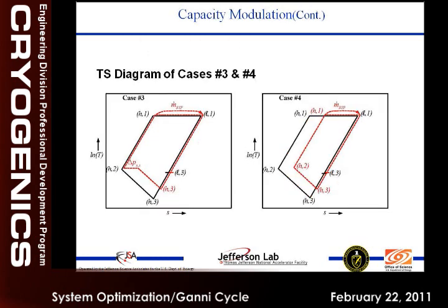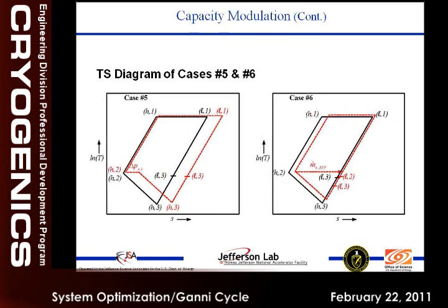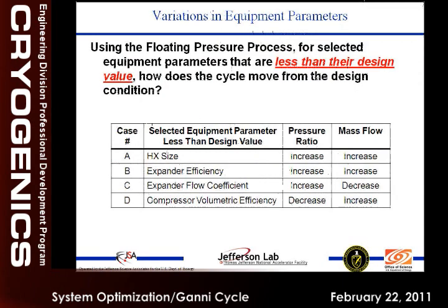So similarly, what they did is they throttled the inlet valve to the turbine to reduce the capacity because it's getting cold, they start adding heat. So it bypasses some at the compressor because as you throttle, it cannot process. And if you go through each thing, they bypass at the turbine level. So there are various mechanisms used, but they do not allow the compressor and turbine to leave where they're designed and vary the charge. That's not what people adopted.